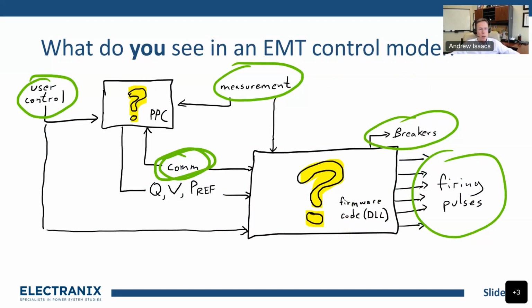That's one reason we started modeling them every time. There's also another effect that can happen where the plant goes into ride-through and comes back out. How the PPC reacts during that period, and how the inverter transfers control back to the PPC, can be interesting — it can create issues, cycling in and out of those modes and so on.